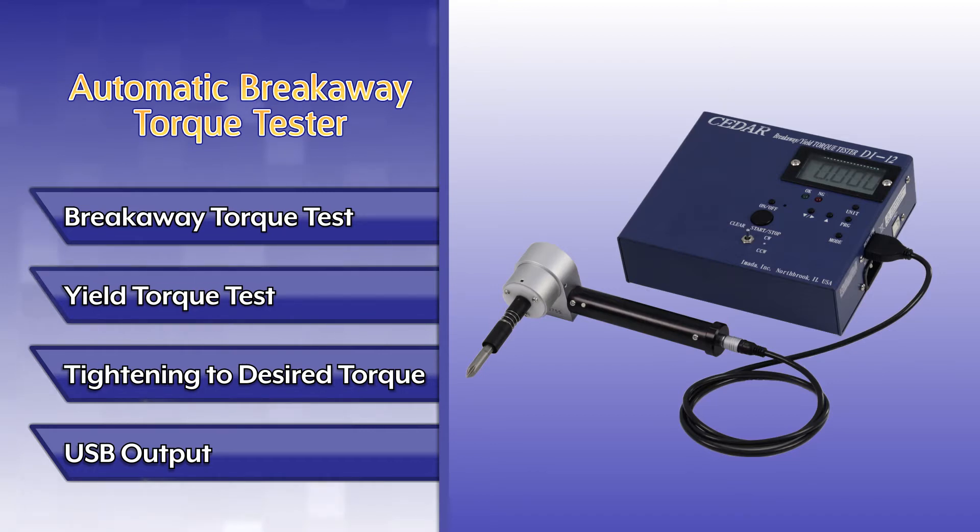The DI-12 can also be used to determine the yield torque of a screw or bolt joint. Determining the yield point of a fastener joint is crucial in determining a target tightening torque. The DI-12 is also able to tighten fasteners to a desired torque value set in the instrument. The DI-12 also features USB output of peak or continuous data.